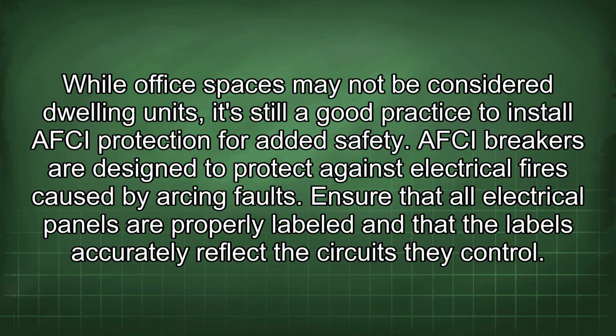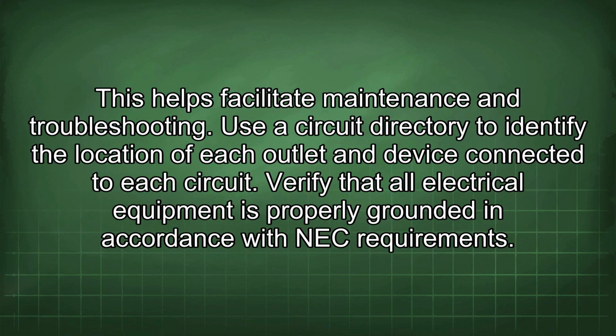Ensure that all electrical panels are properly labeled and that the labels accurately reflect the circuits they control. This helps facilitate maintenance and troubleshooting. Use a circuit directory to identify the location of each outlet and device connected to each circuit. Verify that all electrical equipment is properly grounded in accordance with NEC requirements.